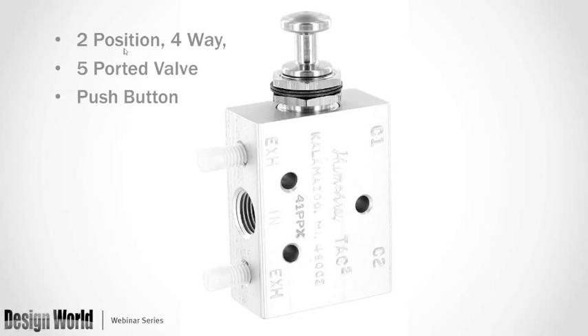Now here, these are little plastic screws, and it's kind of hard to see. It's kind of whited out here, but there's a little slot cut in the side of these little plastic screws. And the more you screw them in, the slower the air comes out. You probably have heard the term when in doubt, meter out. And what we're doing here is we're metering the airflow as it leaves this valve.